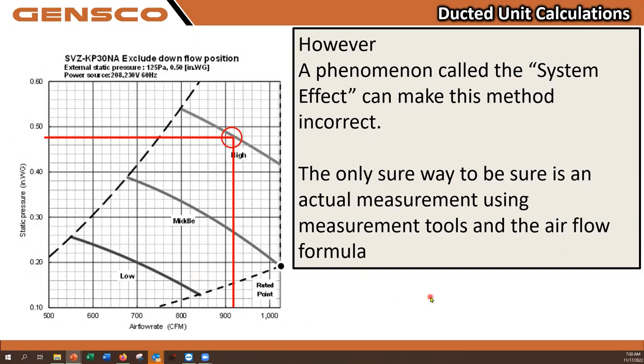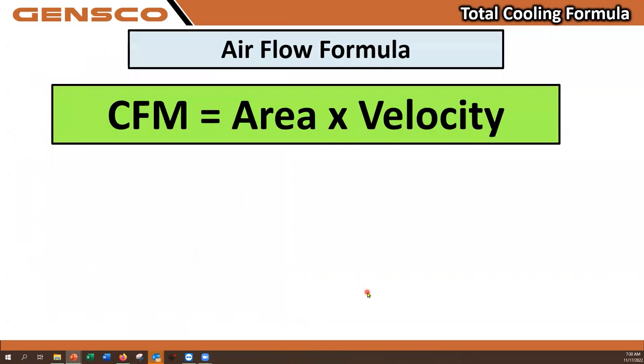Won't hold up in court, however. To do something that's going to hold up in court, you're going to have to actually measure the CFM. Myself, I may measure this and get a number, and then I want to double check that with an actual measurement. So how do you measure it and determine how much CFM the unit's using?